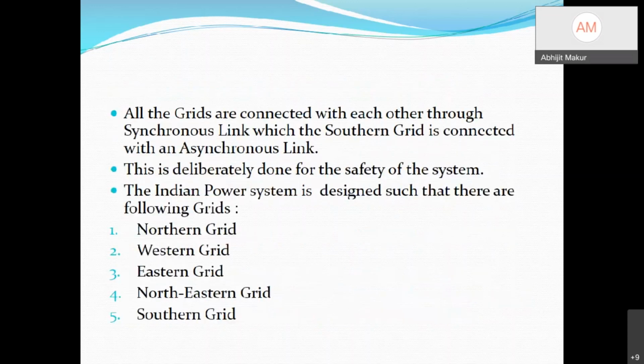All the grids were connected through a synchronous link, while the southern grid is connected with an asynchronous link. This was designed for the safety of the system. The Indian power grid is actually designed with five grids: northern, western, eastern, northeastern, and southern. The southern grid and the other grids are connected by asynchronous links, so when this power fault occurred, all the grids except the southern grid went into darkness, and in the eastern grid, a part somehow isolated itself and was saved.